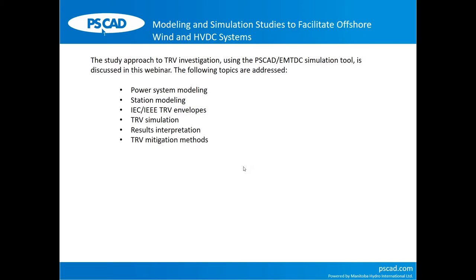the important features that should be included in the study modeling, included in the PSCAD model. And we will discuss where we might find the data to develop the PSCAD study model. Then we will discuss study scenarios, the faults and different scenarios that one should study in order to make sure that your breaker will be able to interrupt a current successfully.